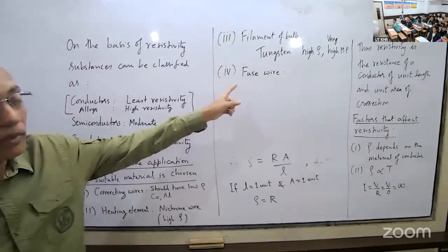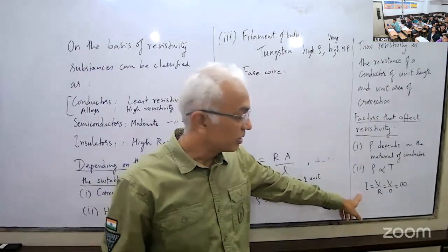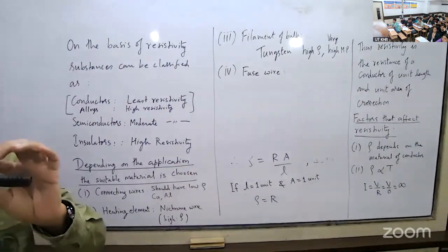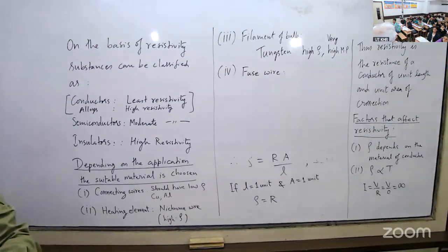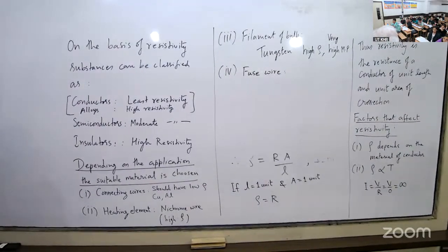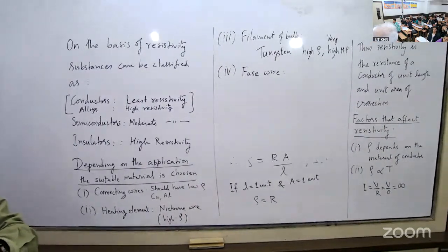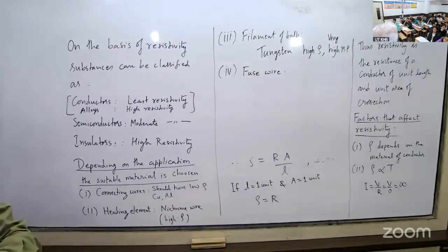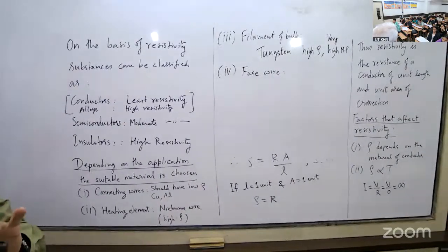So what happens in a short circuit? When high current flows, the conductor becomes very hot. Copper has a very high melting point, and it is running through wood, etc. If it crosses the ignition temperature of the wood, it will catch fire. So before that, in the conductor, what we connect is a fuse. The fuse wire has a low melting point, while the copper conductor wire has a high melting point.